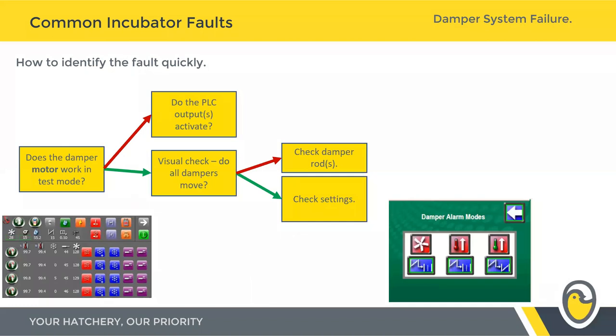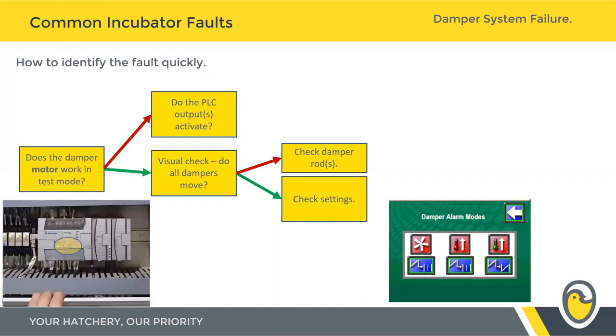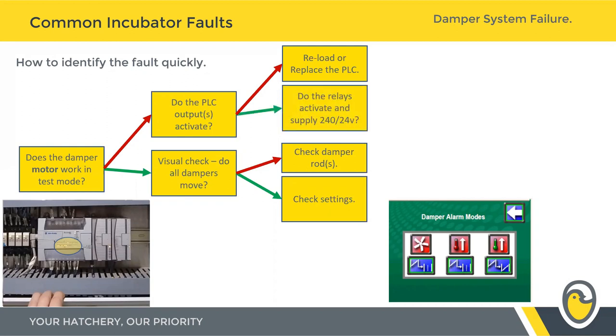Back to the test mode: if hitting test mode shows the damper physically doesn't move, we're back to checking the PLC outputs. On a Gen 3 control, check the little LED lights at the top of the digital output card, put a multimeter across the output and check for 24 volts. On a Gen 4 incubator, the digital outputs are the bottom row of lights and the digital inputs are the top row. If the outputs don't activate, first reload the PLC using the on-site memory cassette. If that doesn't work, replace the PLC. If the outputs do work, check the 24 volts is supplying the relays and then check the relays are supplying the required 240 or 24 volts out to the damper.